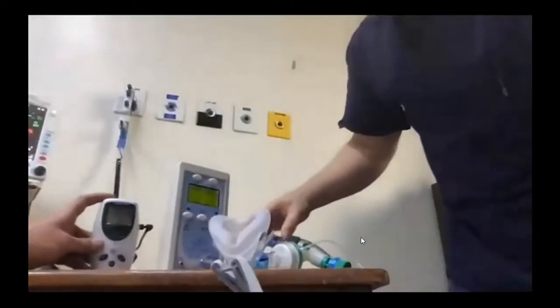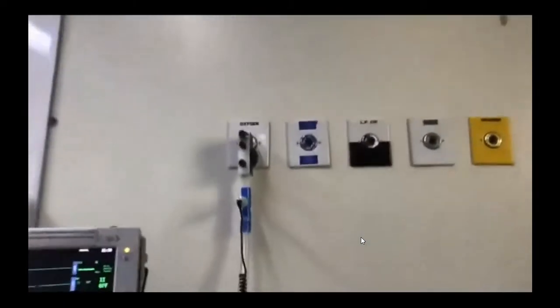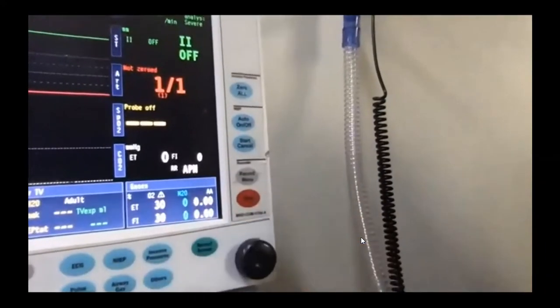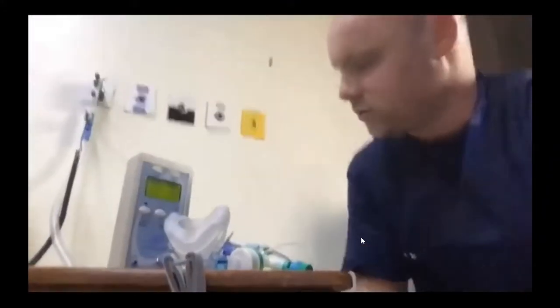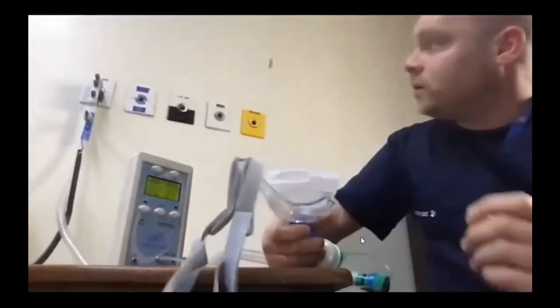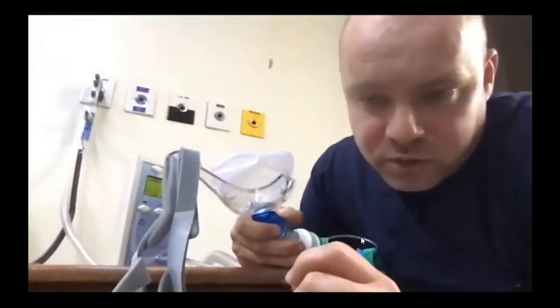If I start enriching the oxygen now, because I've pretty much set more flow than I needed, if it was a patient working a bit harder, you might need to go up a little bit more on the flow. But I'm going to slowly start enriching the oxygen supply. If you can see the side stream analyzer, it was at 32% with zero O2 enrichment. I'm going to slowly enrich it so that you can see. I'm going to open the O2 enrichment knob slowly.